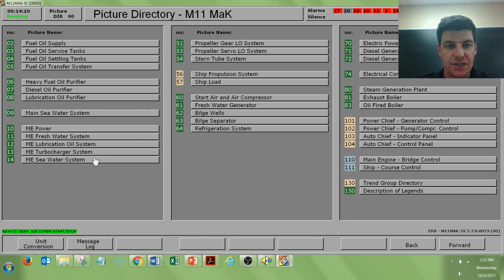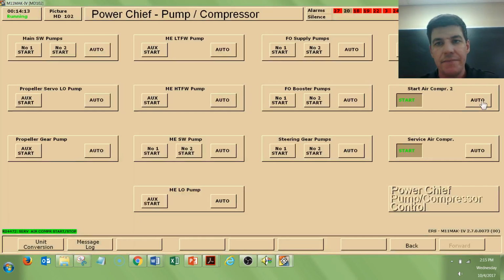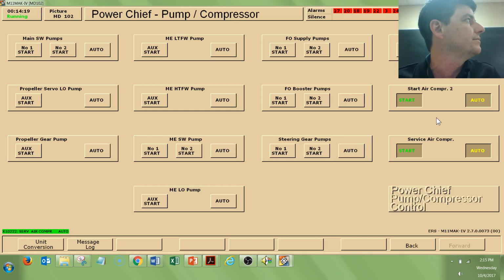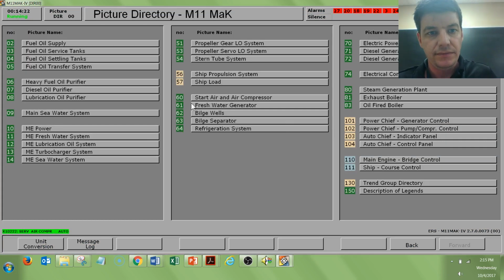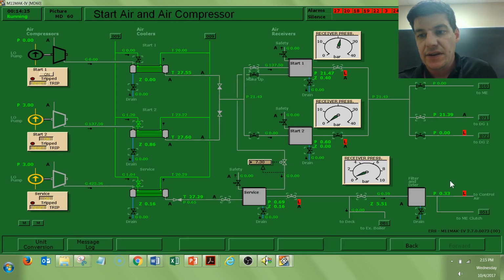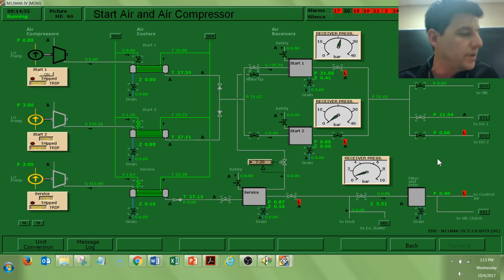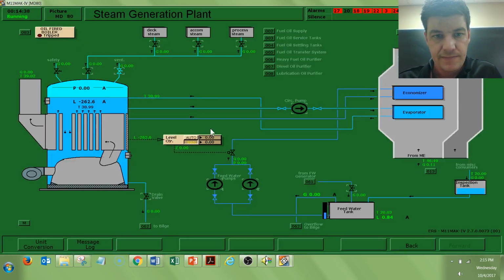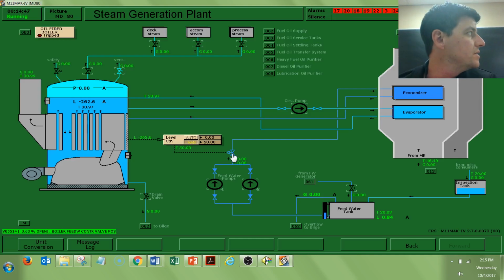And now let's see. If we go to 102, I should be able to get these guys into auto, so prevent me from overfilling those tanks. I can confirm that I have some air pressure here, which means that I can operate my boiler control valve on the feed water side. So this valve would be able to open. Doesn't react very quickly, but at least it's moving at this point. I can turn on my pump, and my level should start to increase.